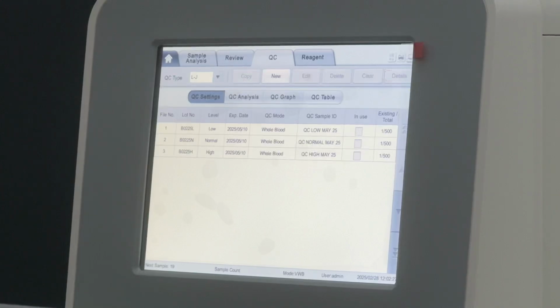This is important because as a supplier we want to do this, and we are educating the GP also. In case we had 2 analyzers, we could do a comparison, but now we only have 1 analyzer. How are we going to compare? We can't, so the only way to compare is with these parameters. QC is very important. So every 3 months they will come and do it, and we will give you continuous support for this QC without charging anything.